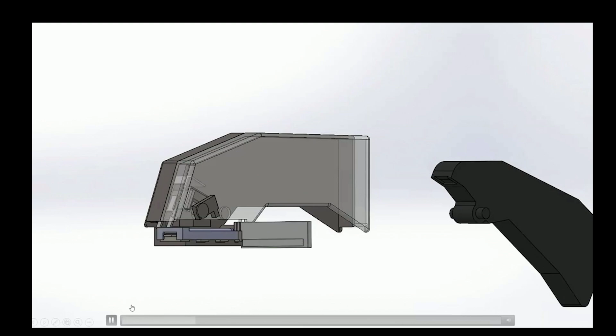Here is our stapler prototype. The outer components, such as the shell, handle, and cartridge, are made from a polycarbonate carbon fiber blend. The internal components, such as the pusher and the anvil, are cut 2D from stainless steel for mechanical integrity and fabrication simplicity. Equally important, here's our staple forming jig. Our staple forming jig is made from PETG and PLA. It allows for the fabrication of 25 uniform staples per cycle, ensuring that the device and its consumables can be produced and maintained within the same ecosystem.